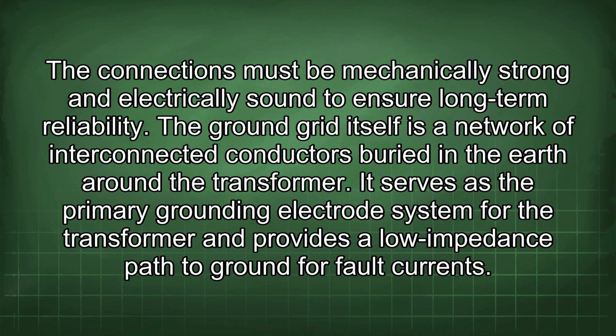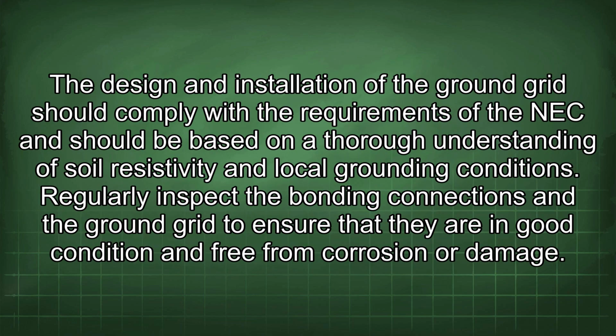The ground grid itself is a network of interconnected conductors buried in the earth around the transformer. It serves as the primary grounding electrode system for the transformer and provides a low impedance path to ground for fault currents. The design and installation of the ground grid should comply with the requirements of the NEC and should be based on a thorough understanding of soil resistivity and local grounding conditions.